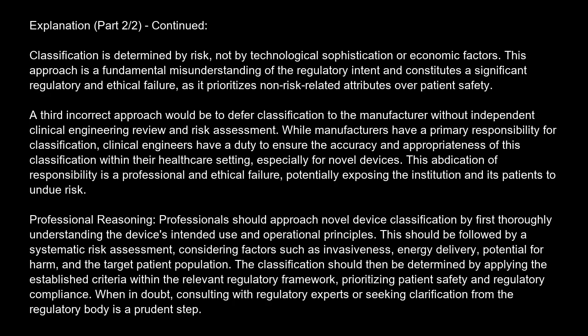Professional reasoning. Professionals should approach novel device classification by first thoroughly understanding the device's intended use and operational principles. This should be followed by a systematic risk assessment, considering factors such as invasiveness, energy delivery, potential for harm, and the target patient population. The classification should then be determined by applying the established criteria within the relevant regulatory framework, prioritizing patient safety and regulatory compliance. When in doubt, consulting with regulatory experts or seeking clarification from the regulatory body is a prudent step.